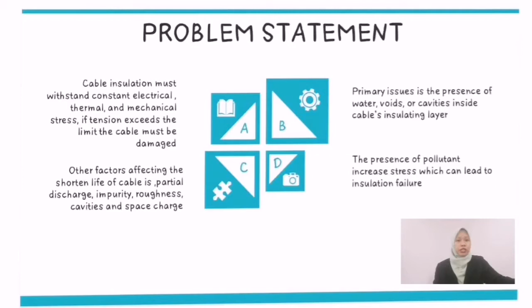The electrical stress is greatest at the conductor surface and at the sheath inner radius. As a result, there will be a substantial difference between the maximum and the lowest stress in insulation. Then, one of the primary issues is the presence of water, voids, or cavities inside the cable's insulating layer. The presence of pollutant also increases stress, which can lead to insulation failure.